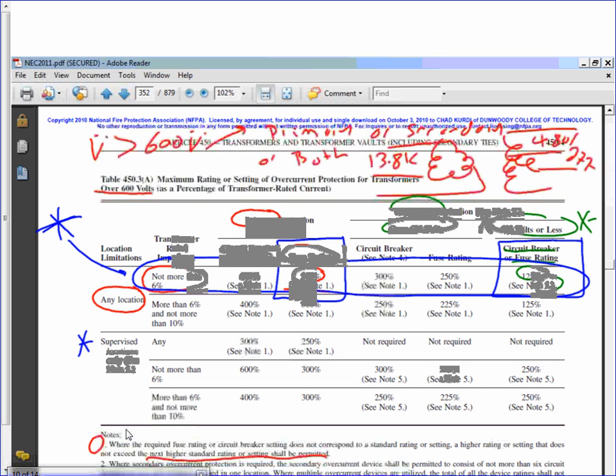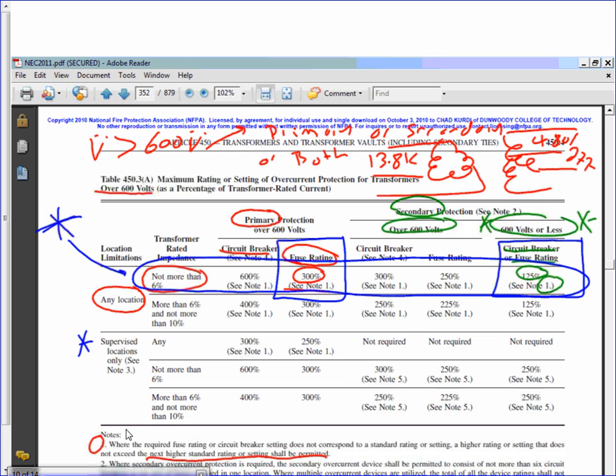Everybody knows the fuses. Now we size the cable. Reminder, I'm using fuses on the primary side. And what's the multiplier for the fuses? Looks like 300%, right? So remember where the 300 came from. On the secondary side, you guys remember what the multiplier is here? 125. Fuse or circuit breaker, I don't care here. Here they distinguish. If it's a breaker, they do 600. If it's a fuse, they do 300. Do both of them have note number 1? Yes. What does that mean? You can go up.